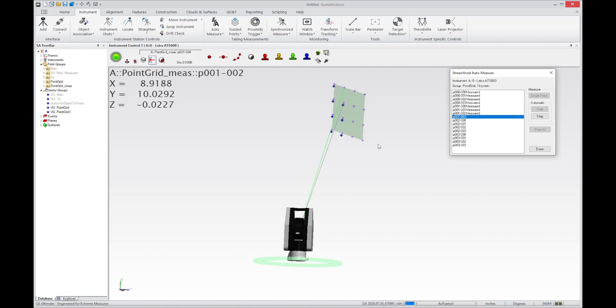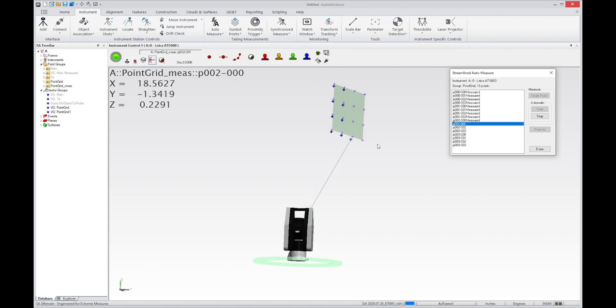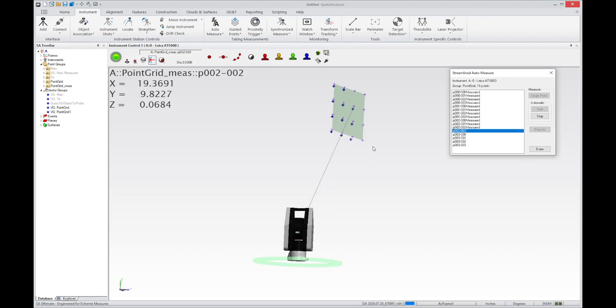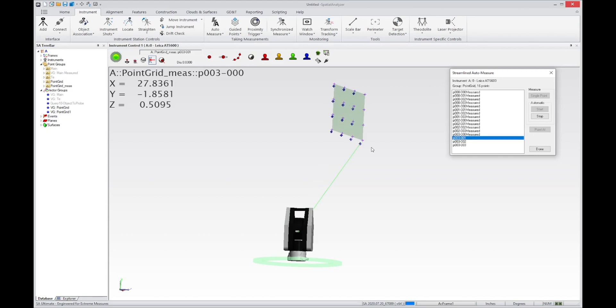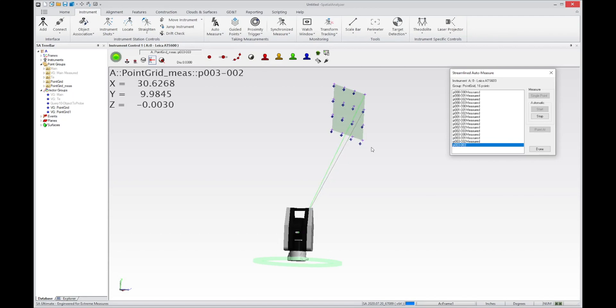the tracker points at the nominal point and will take a measurement directly in line with that point. But if you have any displacement of that surface relative to the actual nominal, then you end up with a little bit of a displacement in the resulting location of the measured points. And that's fine because that's where the actual surface is.